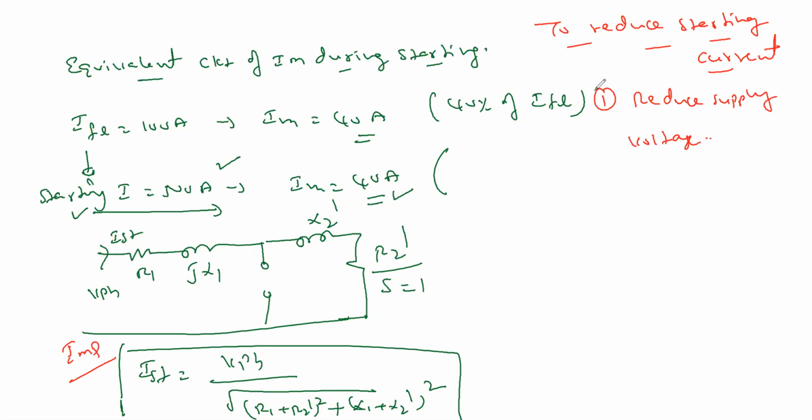मैंने बता दिया already. You have to take current को reduce कर दिया. For example, current is reduced by x times. इधर क्या, voltage reduce कर दिया, तो current x times reduce होगा. Torque क्या होगा? Torque में क्या चल रहेगा? देखो, T start by T full load is I start by I full load whole square. ये वाला expression आ गया ना. For example, starting current is reduced by x times. For example, this is 1 by 2 I_ST over here.